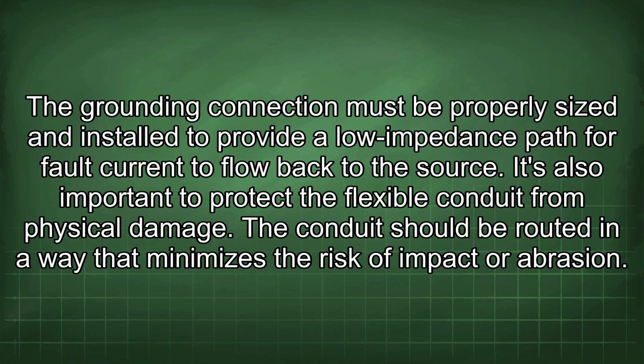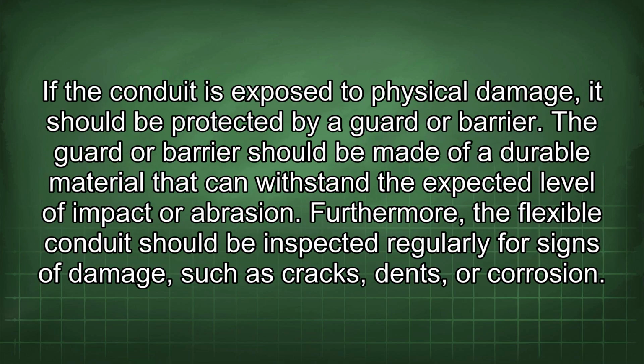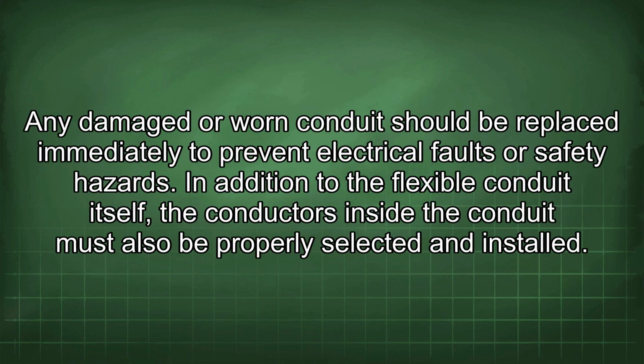It's also important to protect the flexible conduit from physical damage. The conduit should be routed in a way that minimizes the risk of impact or abrasion. If the conduit is exposed to physical damage, it should be protected by a guard or a barrier. The guard or barrier should be made of a durable material that can withstand the expected level of impact or abrasion. Furthermore, the flexible conduit should be inspected regularly for signs of damage such as cracks, dents, or corrosion. Any damaged or worn conduit should be replaced immediately to prevent electrical faults or safety hazards.